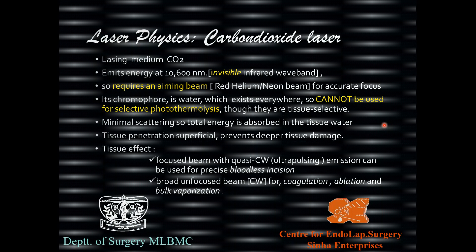Selective photothermolysis means using the laser to selectively cause thermolysis at a specific point containing a particular chromophore while sparing surrounding tissue that lacks it. It depends on the wavelength of the laser beam and the tissue characteristics, especially the chromophore present. CO₂ laser has minimal scattering so total energy is absorbed in water tissue; penetration is superficial, preventing deeper tissue damage. With a focused beam it gives precise incision; with a broad unfocused beam it acts as a coagulator, ablator, or bulk vaporizer.